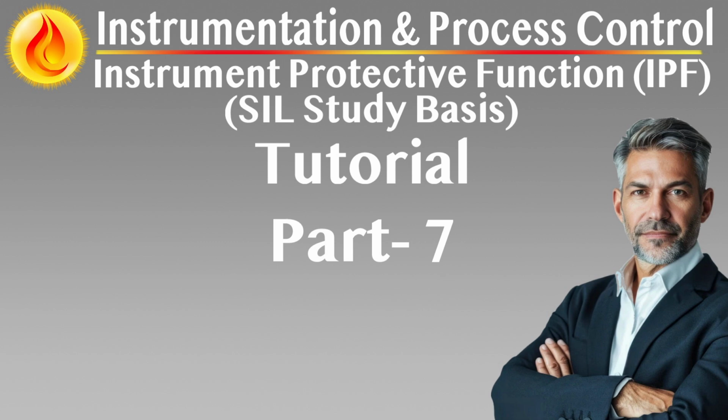Core HMI features for maintenance overrides. Persistent display of active overrides. Any active maintenance override must be continuously visible on operator and engineering HMIs until fully cleared. Display should include IPF tag, affected device or function, override type, manual or automatic, reason for override, start time, and expected restoration time.